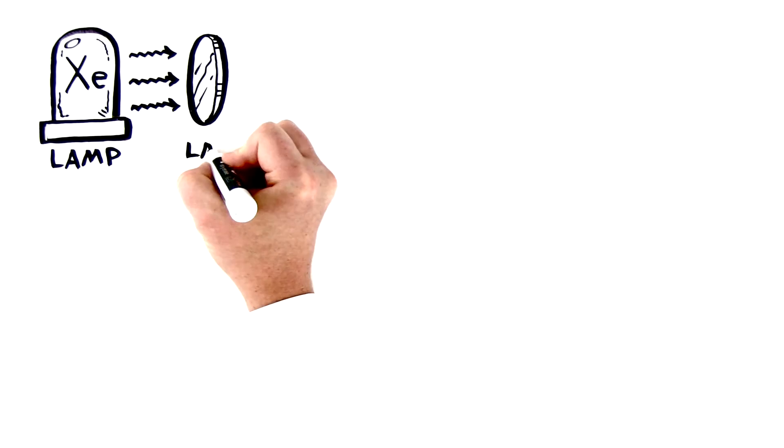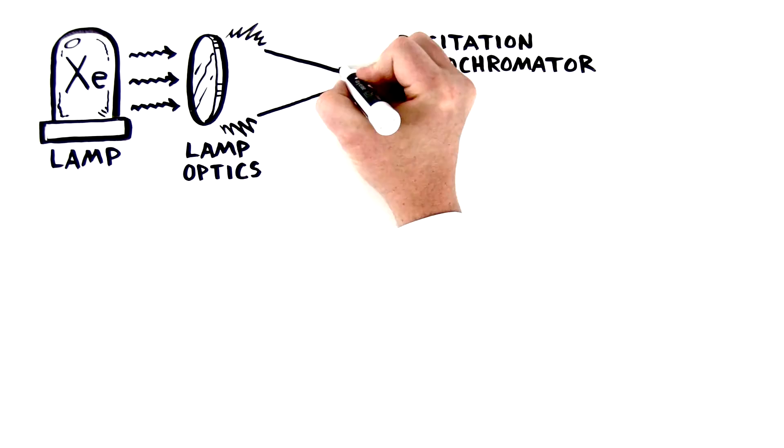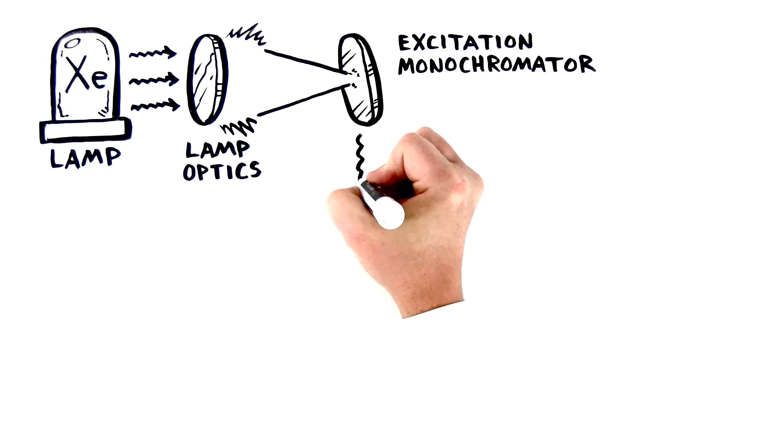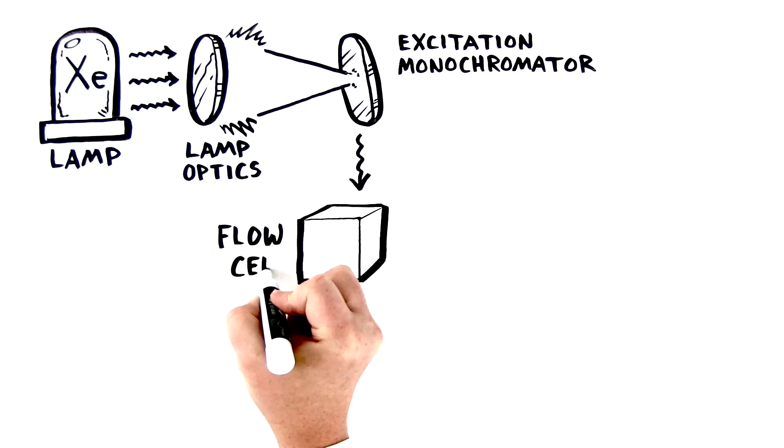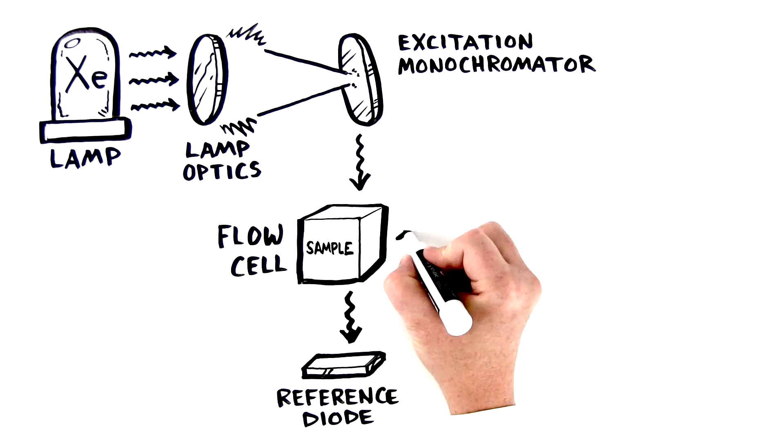In a fluorescence detector, the sample is illuminated by light coming from a xenon lamp. The xenon light is focused by lamp optics. In the light path, an excitation monochromator enables the selection of light of a specific wavelength. Only light of this selected wavelength illuminates the flow cell that contains the sample. A reference diode behind the flow cell measures the intensity of this excitation light.